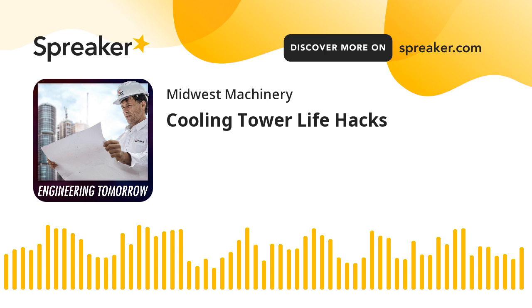The velocity recovery stack can keep you in a smaller box size by increasing efficiency, so it's usually not a trade-off where you'd say just don't give me the velocity recovery stack—because that probably means you're buying a bigger tower just to get the portable davit. So it's something to consider.